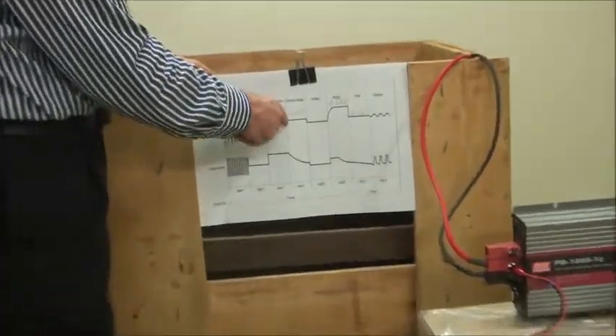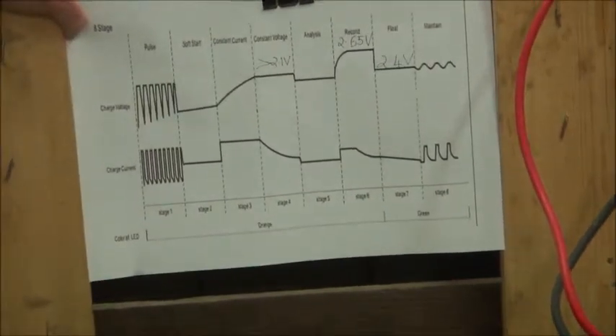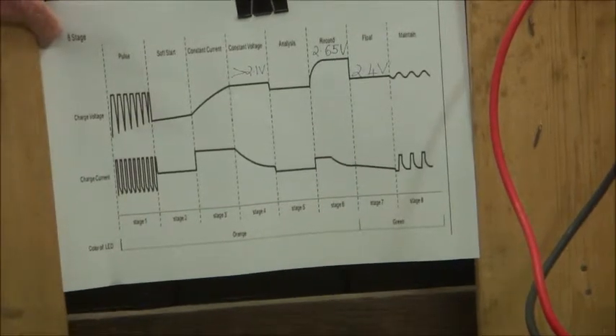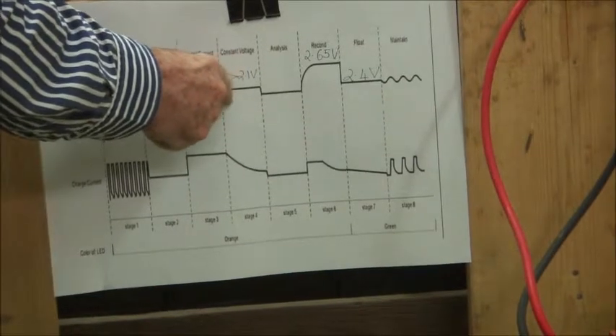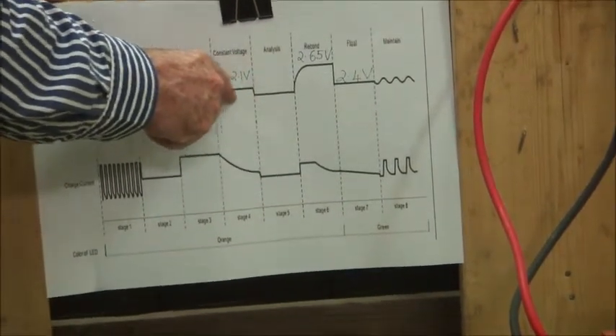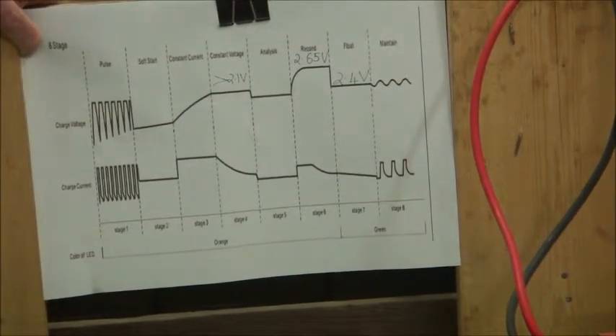It will then eventually reach a minimum of 2.1 volts per cell. That's based on a traction battery minimum voltage. Normally this will be 2.4, but it has to reach 2.1 volts per cell at this stage here, otherwise it will just turn off. It will assume that the battery can't be charged.